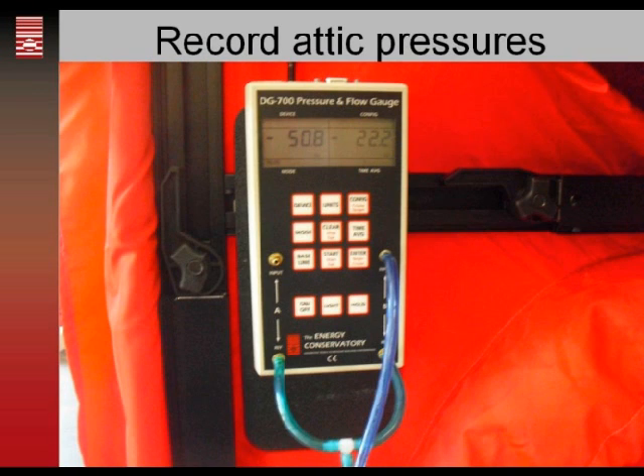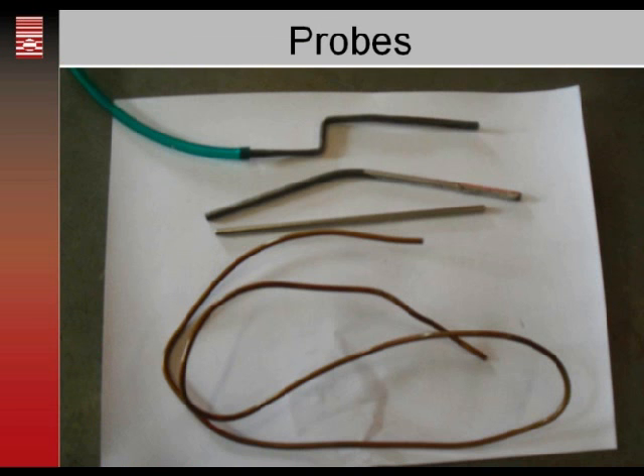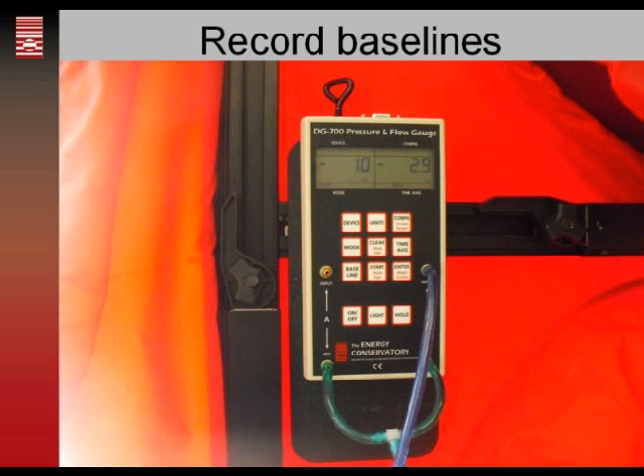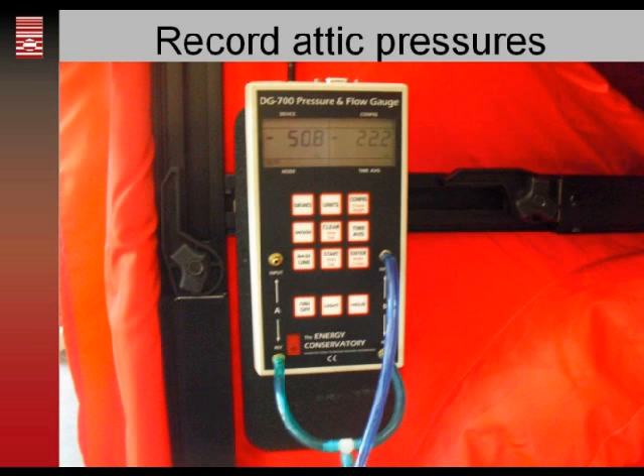Then you'll bring the house to 50, and remember again, we want the house to change by 50. Initially we were at 1 pascal, so now we're bringing it up to close to 51 pascals. On windy days, it's going to be hard to hit it exactly.